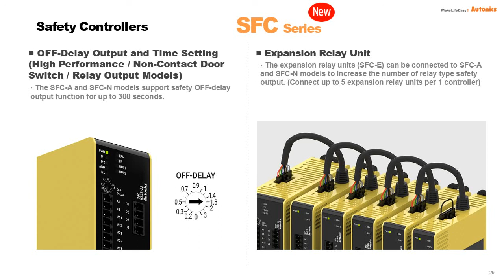In this slide, I would like to show samples of applying our SFC series safety controller to do some logic connection. So please refer to the diagram on the left hand side. Right now in this system, they have two motors, the first priority and the second priority. When the emergency stop switch is triggered, these two motors, which are linked up with the safety light curtains and also the emergency stop button, both of them are stopped. This is because the first priority is the emergency stop switch.